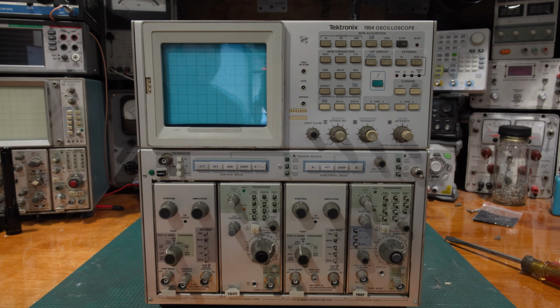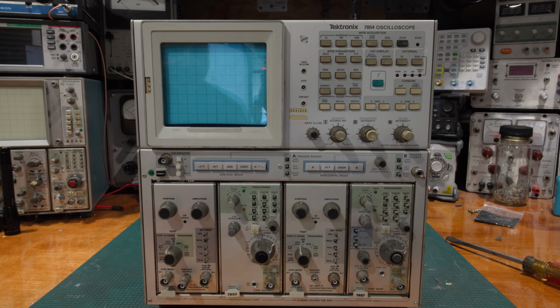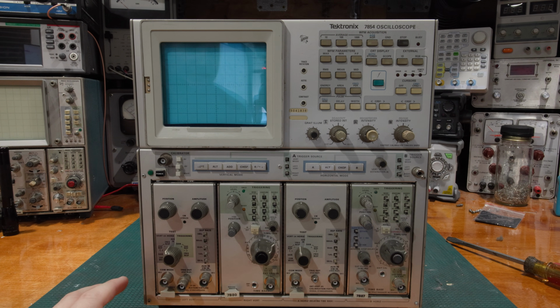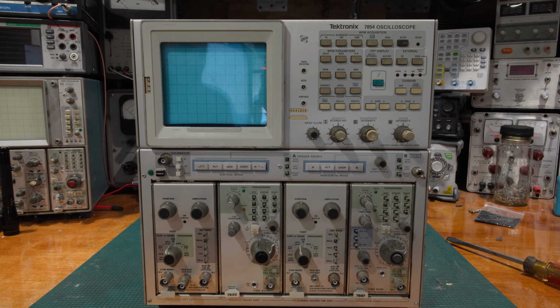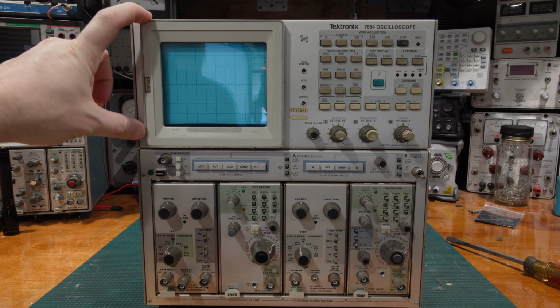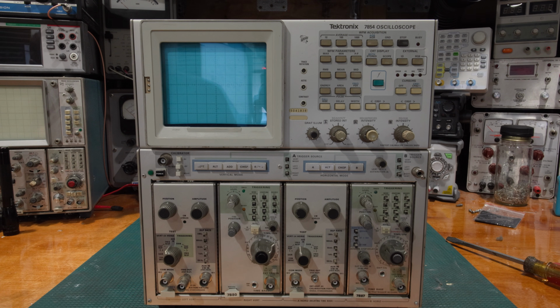Now, the trigger system in this frame is working absolutely flawlessly. It has no problems on it, and that is one of the more fiddly systems to adjust on one of these 7000 series. So sometimes if it's working, it can be best to just let it lie. If it's having problems, absolutely it needs adjustment, and sometimes we have to get into the weeds. But on this particular frame, the trigger system's fine, the calibrator's fine, and they don't even make the film for the scope cameras anymore, so they're not even useful. So probably going to skip the calibrator section and the trigger section.